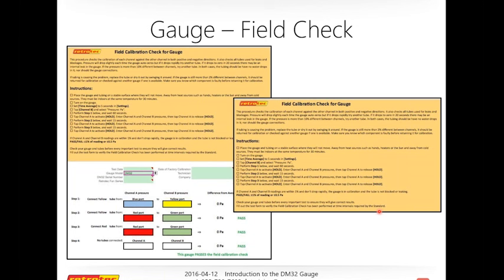So that said, even though they do come calibrated, it is always a good idea to do a field check. I like to do a quick one at least once a week on my gauges because it's so important. To that end, Retrotec has developed a spreadsheet that you can download for free, and the spreadsheet is cut into 2 parts. One part explains your instructions. It tells you what to do, step by step, of how to run the test, and then the second part at the bottom is where you put your information, and it will tell you if it passes or fails, and then you can figure out if one of your tubes is failing or if one of the channels is not correct.